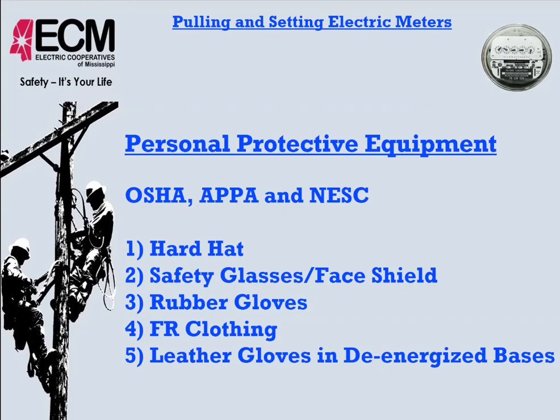Okay? So OSHA, the APPA safety manual, and the National Electric Safety Code identify some safety equipment, personal protective equipment, that we should have on while setting and removing meters. First thing is a hard hat. We know that pretty much anytime we get out of the truck we should have that on. Safety glasses and face shield, use those in combination with each other, unless the safety glasses are protecting you from UV rays as well, the bright light of the arc flash.